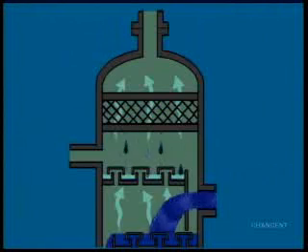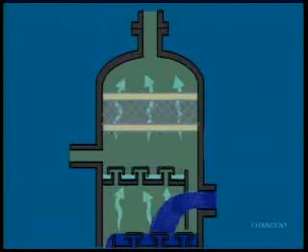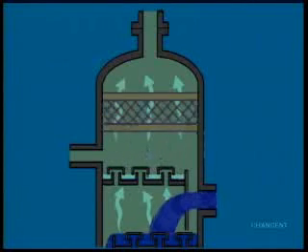There is usually space in the overhead system for separation, where most of the entrained amine solution particles in the vapor stream will settle out. Amine solution not settling out will be removed by a mist eliminator. This prevents liquid amine from being carried out of the stripper and into the overhead vapor line.